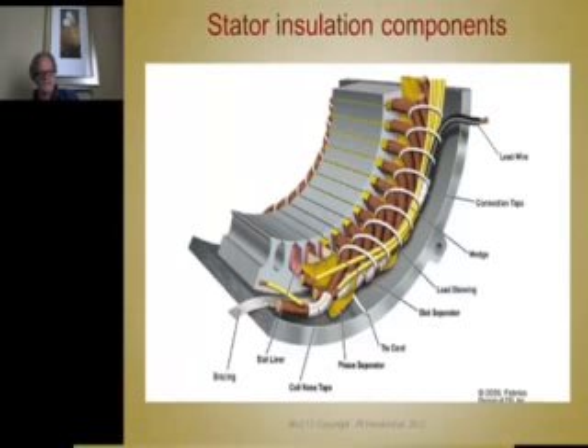Obviously these are the coils. These coils can be made up of multiple strands in parallel, or maybe a single strand per turn. That could be just a lot of turns for a high voltage motor, or a low number of turns with parallel strands. It looks like, if this is the lead coming out of it, it's a combination of both. It looks like there are several parallel strands per turn, this being a turn.